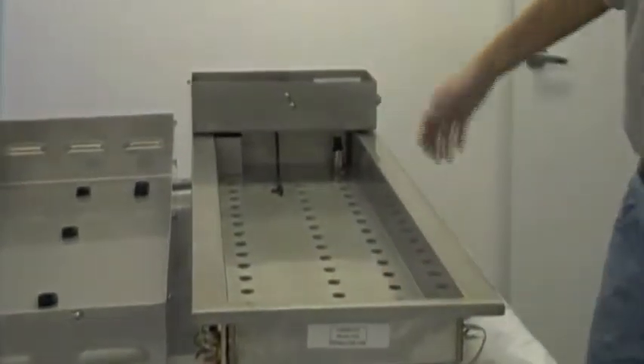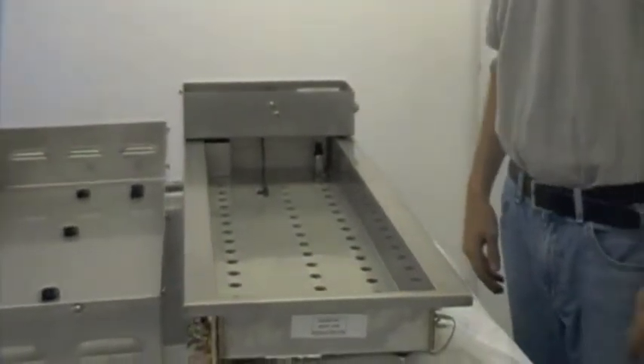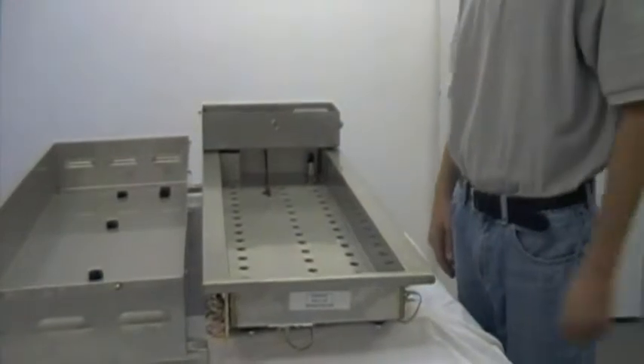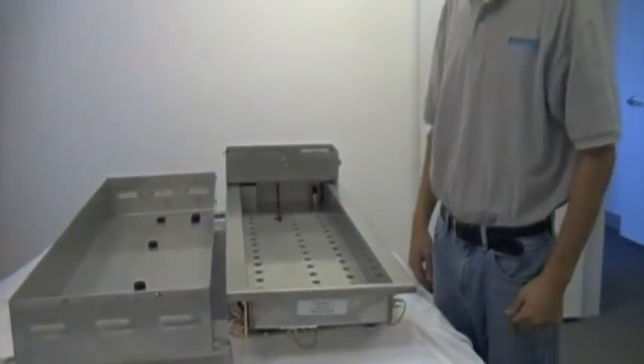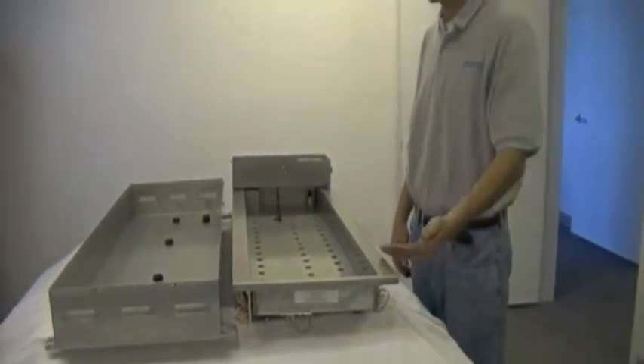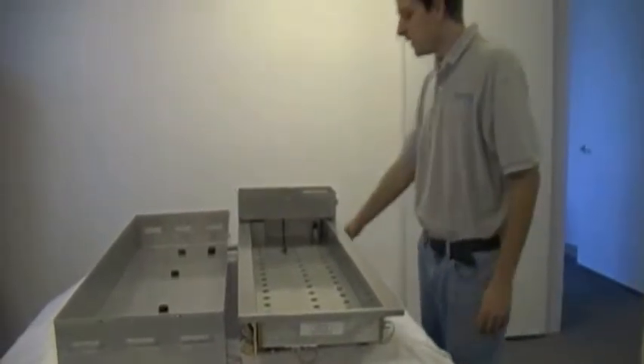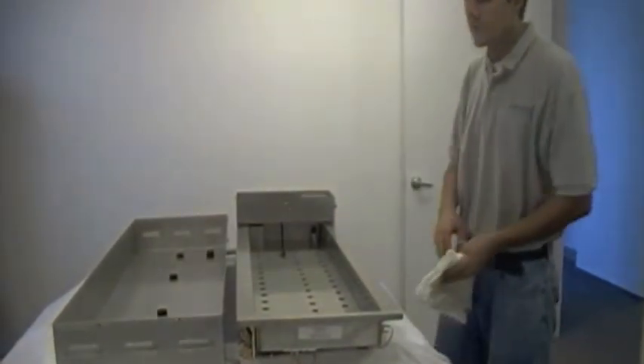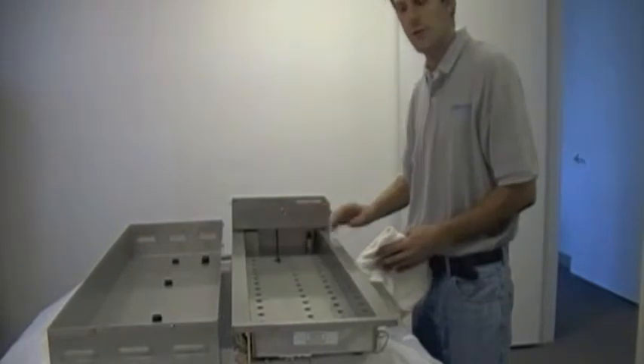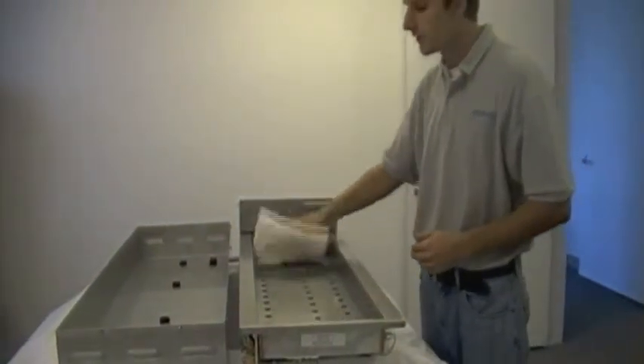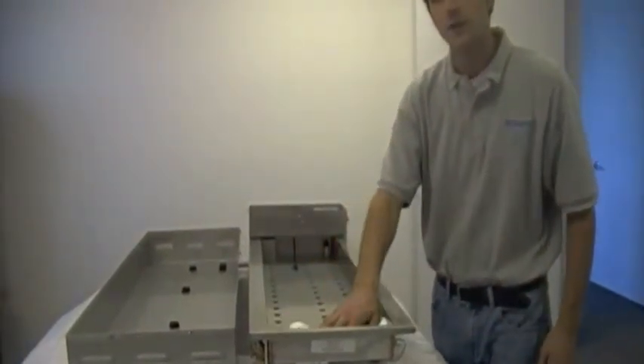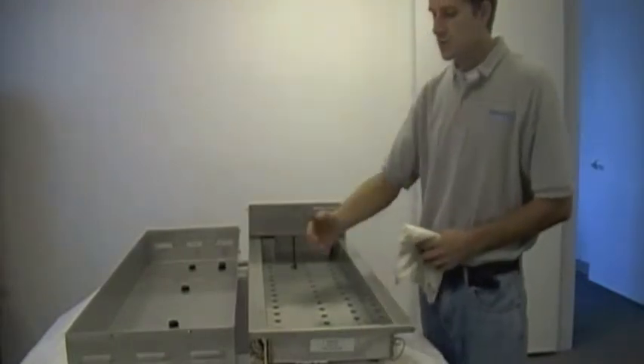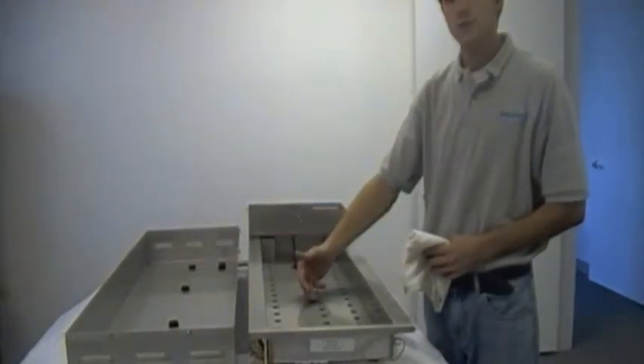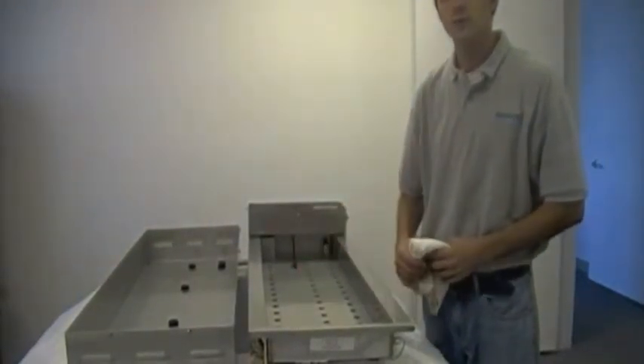The only other requirement for taking care of an ultrasonic humidifier is occasionally cleaning it, depending on your air and water quality. Purified water and clean air will require very little cleaning. In order to clean the humidifier, you never want to spray any chemicals on the inside of the pan. Simply take a damp cloth and wipe down any buildup that may occur. Never touch the actual surface of the piezo disc with any tools or your finger, as you can very easily damage it.